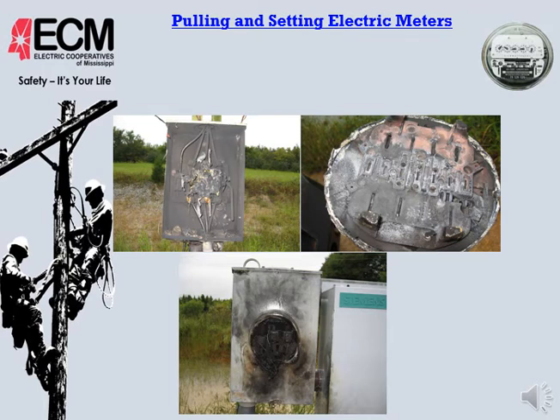This photo is actually a 3-phase meter, HQ7 7-lug meter base, and I left this one in here because I wanted you guys to see this. Notice the photo to the top right, the back of the meter. It burnt every single spade off the back of the meter. This is definitely something we don't want to be standing next to when it happens. 3-phase fault current can be tremendous, so keep in mind this can happen on single-phase or 3-phase meters, either one.